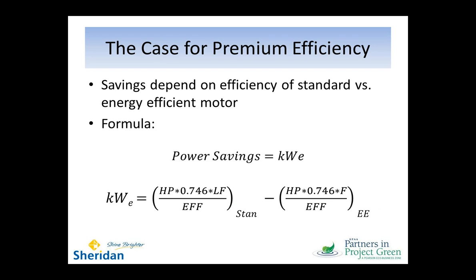This brings us around to establishing the case for why we might want a premium efficiency motor. Why would we consider that? Life cycle thinking actually makes it pretty straightforward to evaluate the economic value of using these. And so I've shown some of the sample calculations that you might undertake. And the formula is actually really quite simple. It's a comparison of how many kilowatts you'd expect to consume with a standard efficiency motor minus the kilowatts you would expect to consume in an energy efficient case.